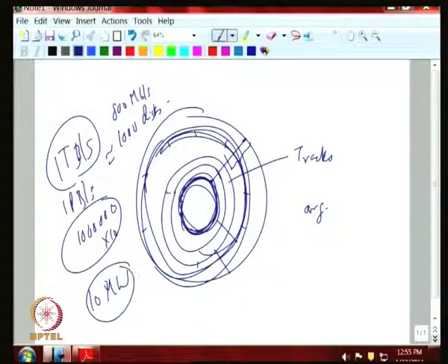Now this looks like a minor number, but actually 10 megawatts you have to cool it also. That means you need air conditioning also, because the air conditioning also requires power. You add all that power for air conditioning, all this stuff, it turns out to be not 10 megawatts, it will be some multiples of 10 megawatts, 20 megawatts sometimes. You need that kind of power to run this.